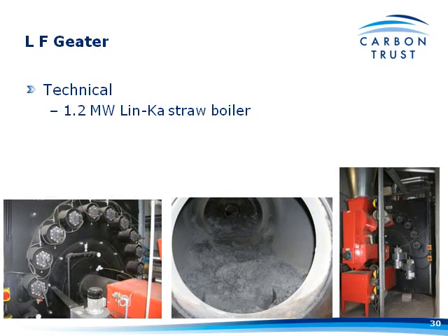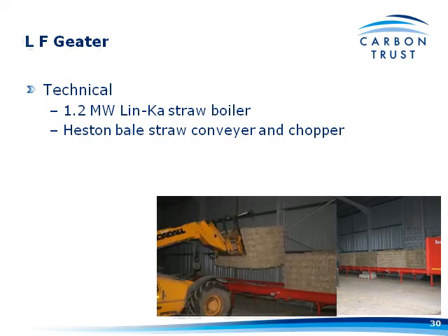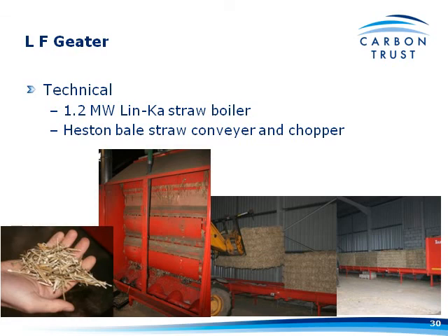Inside the boiler it was in the middle of a clean-out and had a problem with clinker build-up. It has automatic tube cleaning — the shotgun-effect tube cleaning that Matt was talking about earlier. These burn what we call Heston bales — 550-kilogram straw bales — manually loaded onto a conveyor that holds 15 bales, which is enough for about 18 to 20 hours of burning at full output. The bales steadily make their way down the conveyor into the straw chopper. The straw is chopped up and blown through into the fuel delivery system.